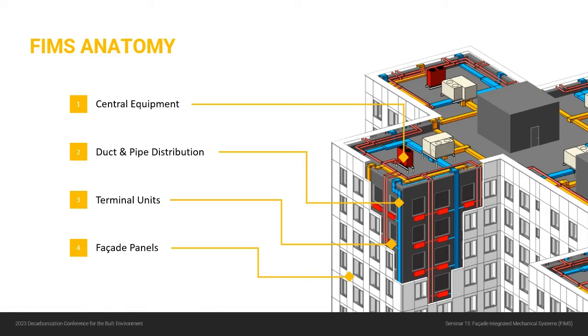Now there are 4 main components of a FIMS system. We have the central equipment, which is generating the heating, cooling, and ventilation, and that then gets distributed through duct and pipework that is located outside of the existing facade, but within that new overclad facade, so within a cavity formed between the two. And that's bringing it to the terminal units, which are delivering that conditioning into the space. And then all of that is enclosed within that new, insulated outer shell around the building.